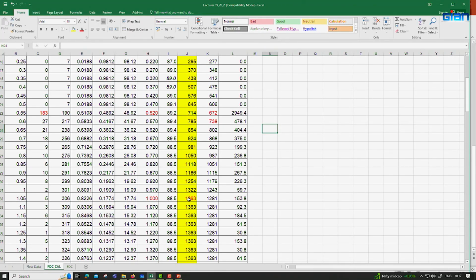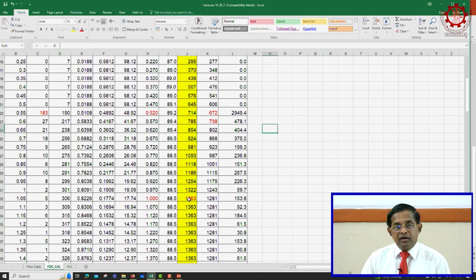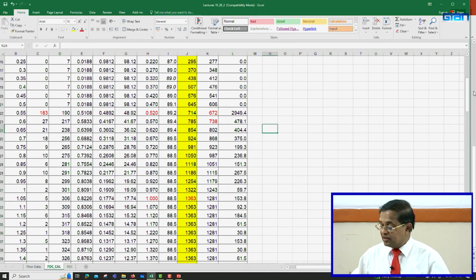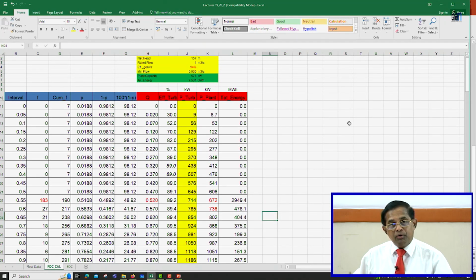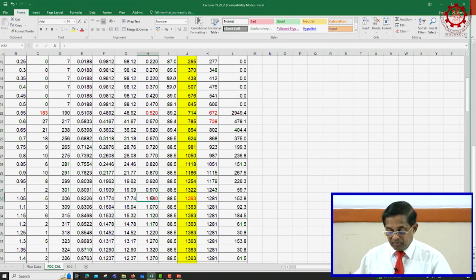So now we told that earlier we can even put two machines, right. Say we decided here to put one machine of 400 kilowatt, another machine of 1000 kilowatt, rounding off to 1400 plant capacity, right. In that case, how do we adjust this to reflect the new condition, right. So then we can get the efficiency curves of both turbines, small turbine and the bigger turbine. So, small turbine has now a different rated flow, right. We have assumed here 1 cubic meters per second as our rated flow, right.